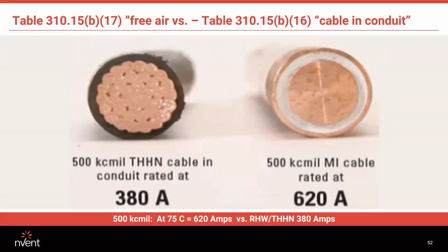So a good rule of thumb is if you're working with 480 volts, 300 feet or less, you can pretty much take the free air rating at face value, as 3% voltage drop is acceptable. 208 volts, 125 feet. Now, of course, on our website, pyro10x.com, we've got a voltage drop calculator where you can just plug in the run length, the voltage, the current, hit the calculate button, and it'll tell you what your voltage drop is.